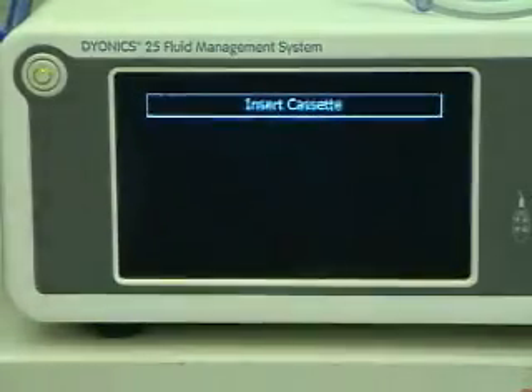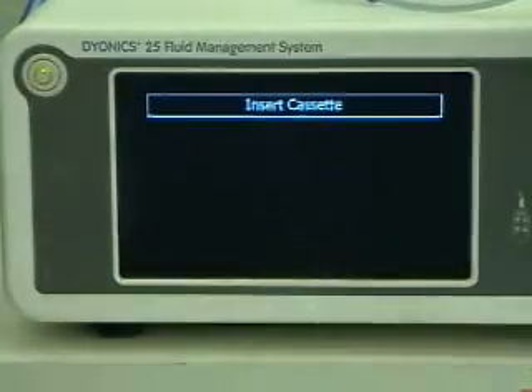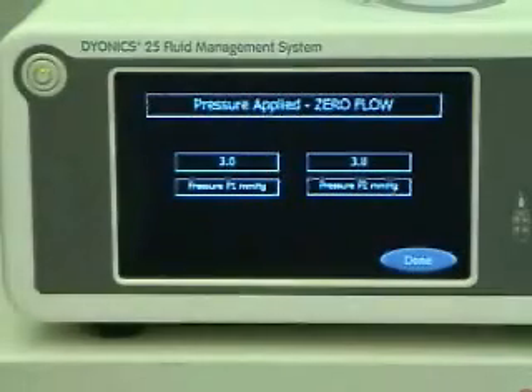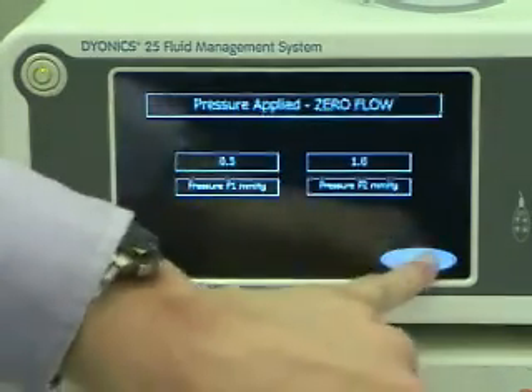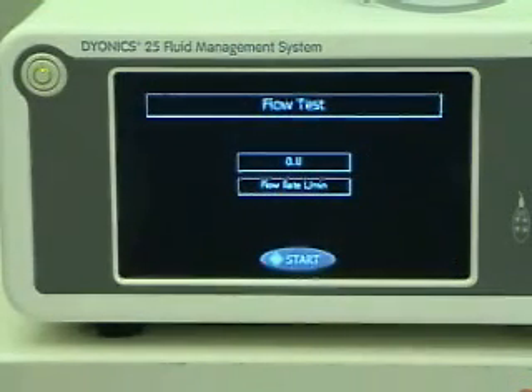It asks you to insert a cassette. So I'm going to put a cassette in the side, then flicks to the next screen. It's telling you what the pressure in the system is with 0 flow. So again, both of those numbers are less than 10, and the transducers are in calibration. When we press done, it then asks you to do a flow test.